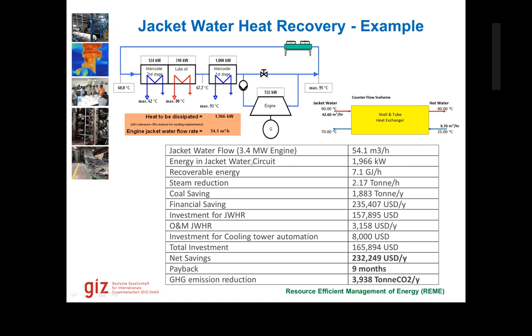Typically for this 3.4 megawatt engine, we got a quotation of 165,000 USD, including the investment for automation of the cooling tower. Because if we do this, we also need to automate the cooling towers, just in case we sometimes have low demand of hot water in the processes. The cooling towers must directly kick in at that time and start doing the cooling, rather than using this heat recovery system.